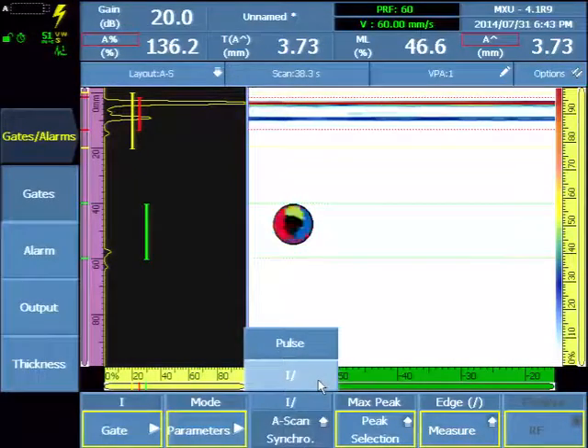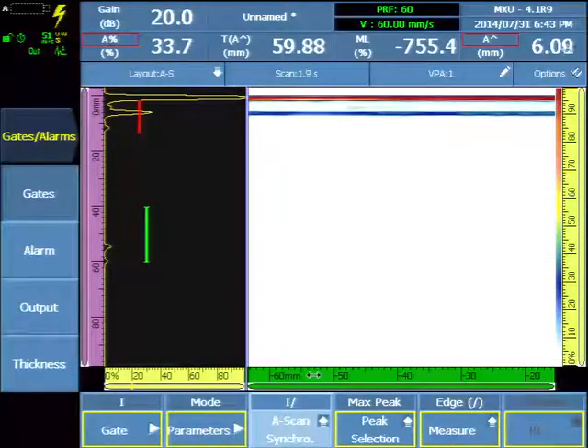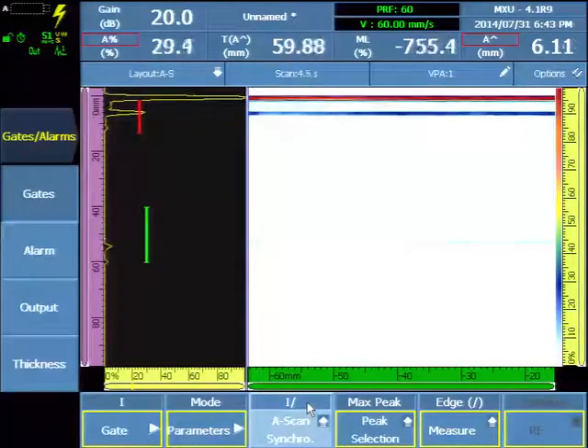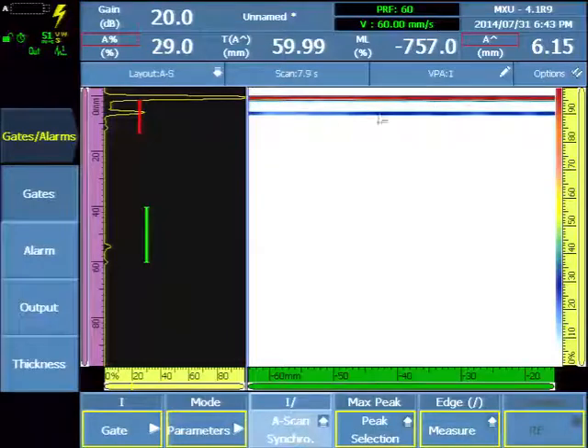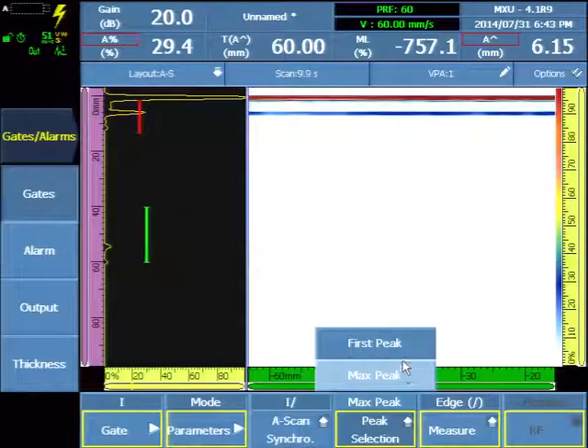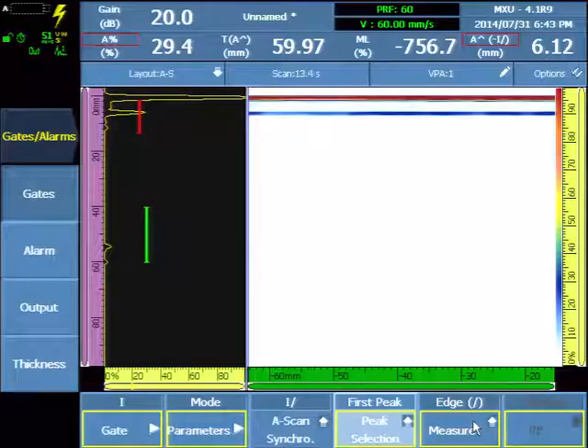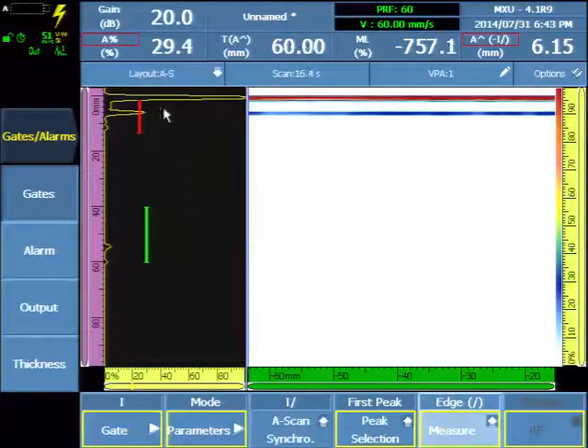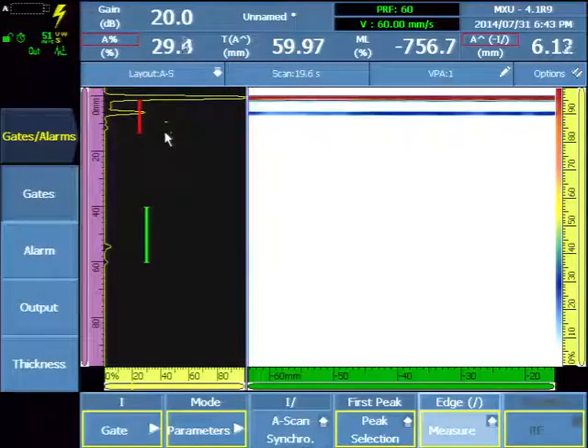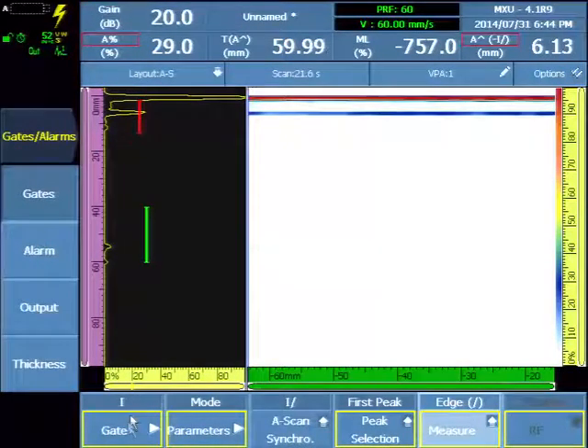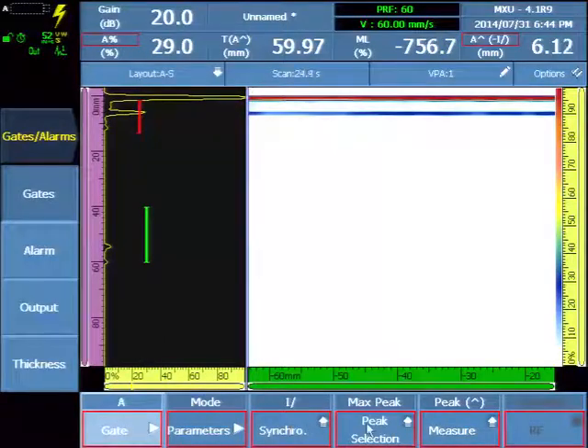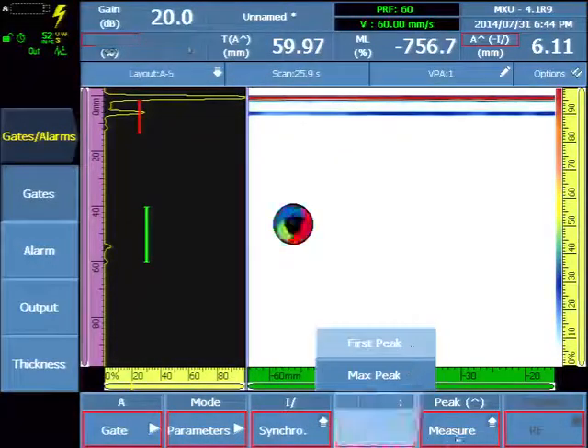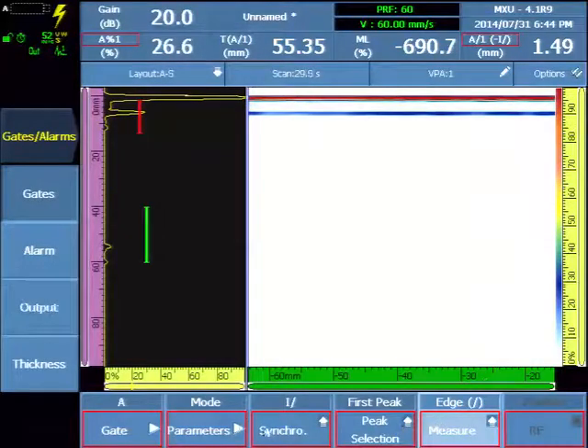At this point no wedge delay is stored because it's dynamically adjusted and as I move the probe now my interface is flat regardless of if the probe is even or not. We're going to use the first peak of the signal in the gate and edge mode and it's normal that the yellow synchronization gate is not visible while we're in this mode. And we will change the same measure modes for our detection gate A.